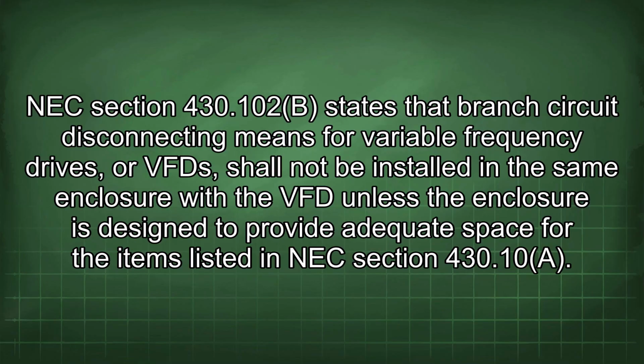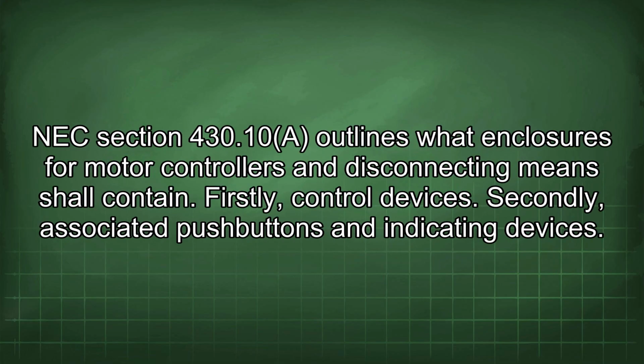NEC Section 430.102(b) states that branch circuit disconnecting means for variable frequency drives, or VFDs, shall not be installed in the same enclosure with the VFD unless the enclosure is designed to provide adequate space for the items listed in NEC Section 430.10(A). NEC Section 430.10 outlines what enclosures for motor controllers and disconnecting means shall contain.